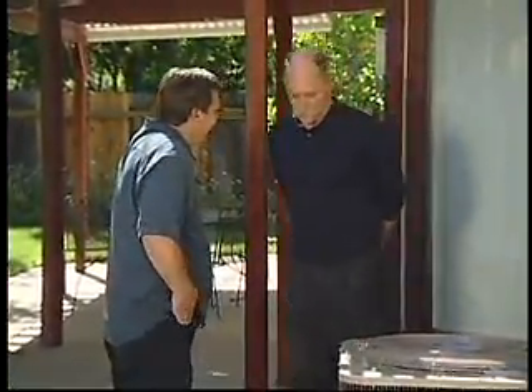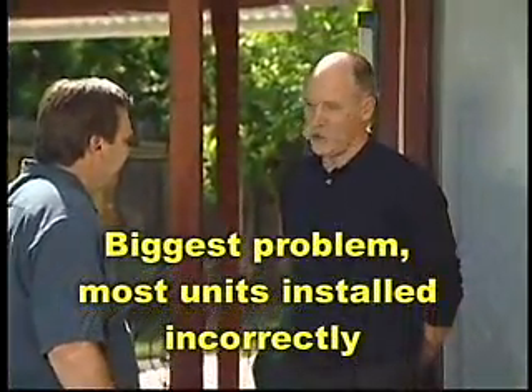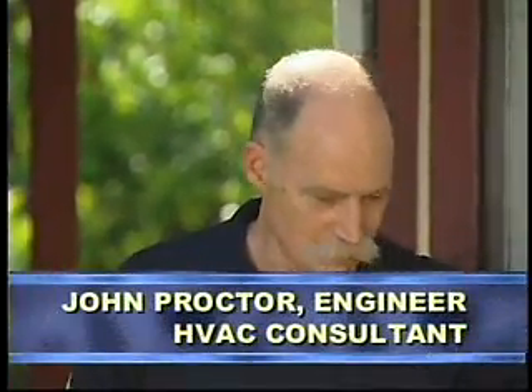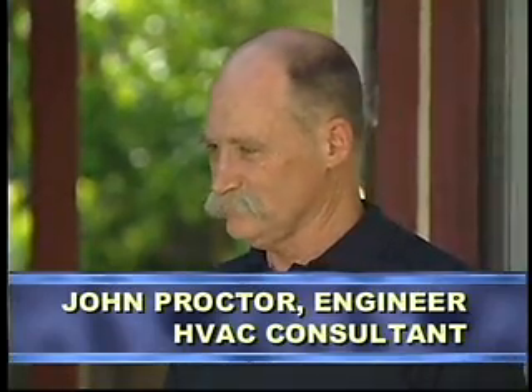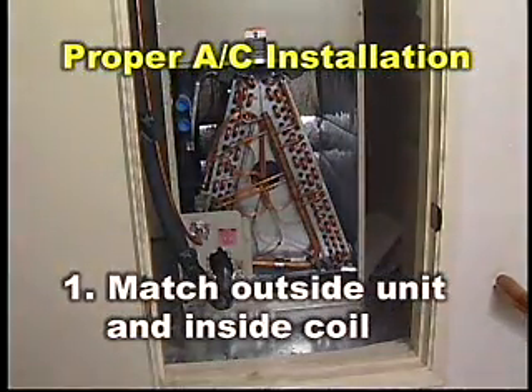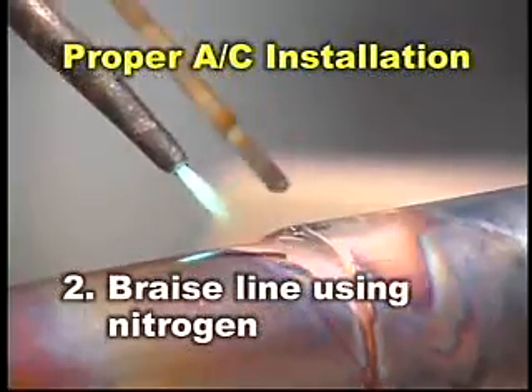Yeah, absolutely. Well, the biggest problem is that the vast majority of them are installed wrong. Basically, a standard installation involves setting the outside unit, bringing a set of lines out, brazing it together, opening the valves, turning it on, and seeing if you get cold air. Now, that just doesn't make it. What you really need on a proper installation is, first of all, you have to match the outside unit and the inside coil. Second thing you have to do is braze the lines using nitrogen. So when you flow nitrogen through it, you don't get little pieces of carbon that'll end up clogging the unit and making it not work right.